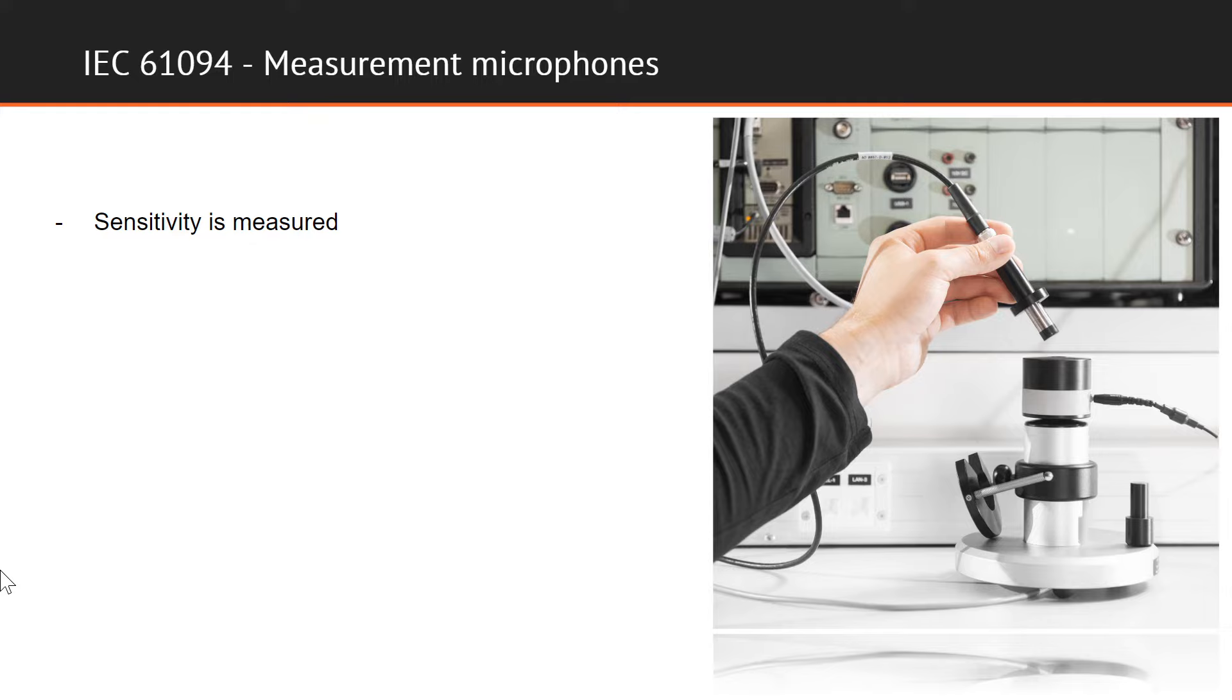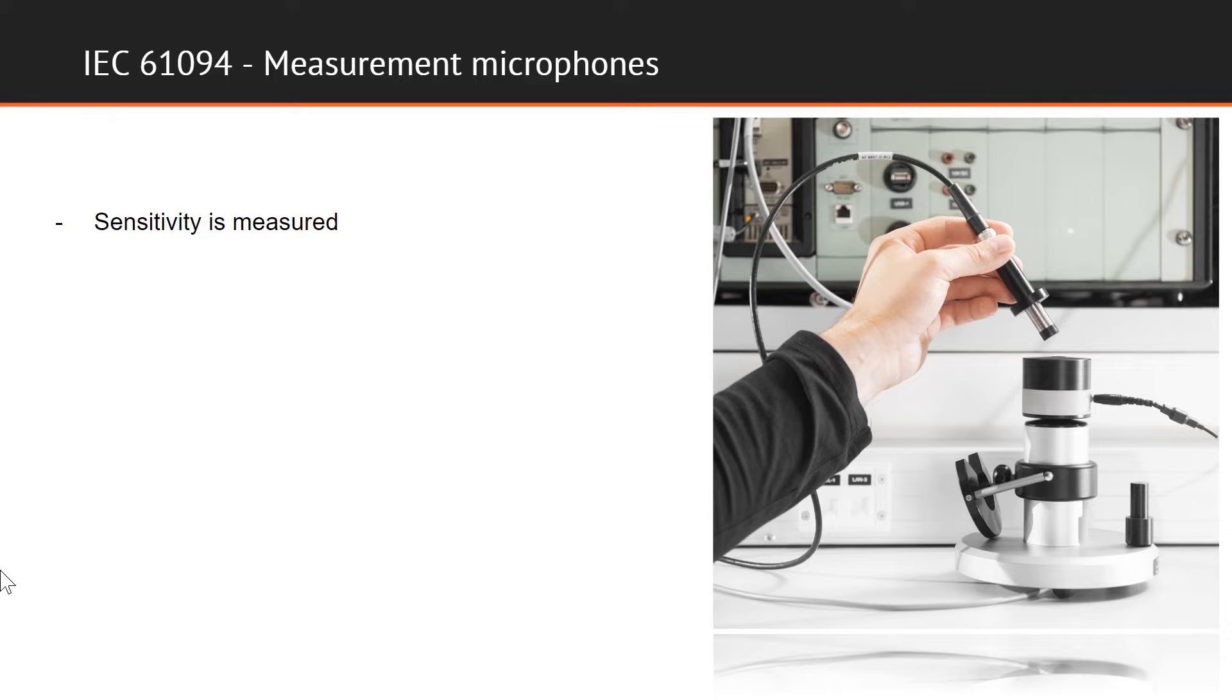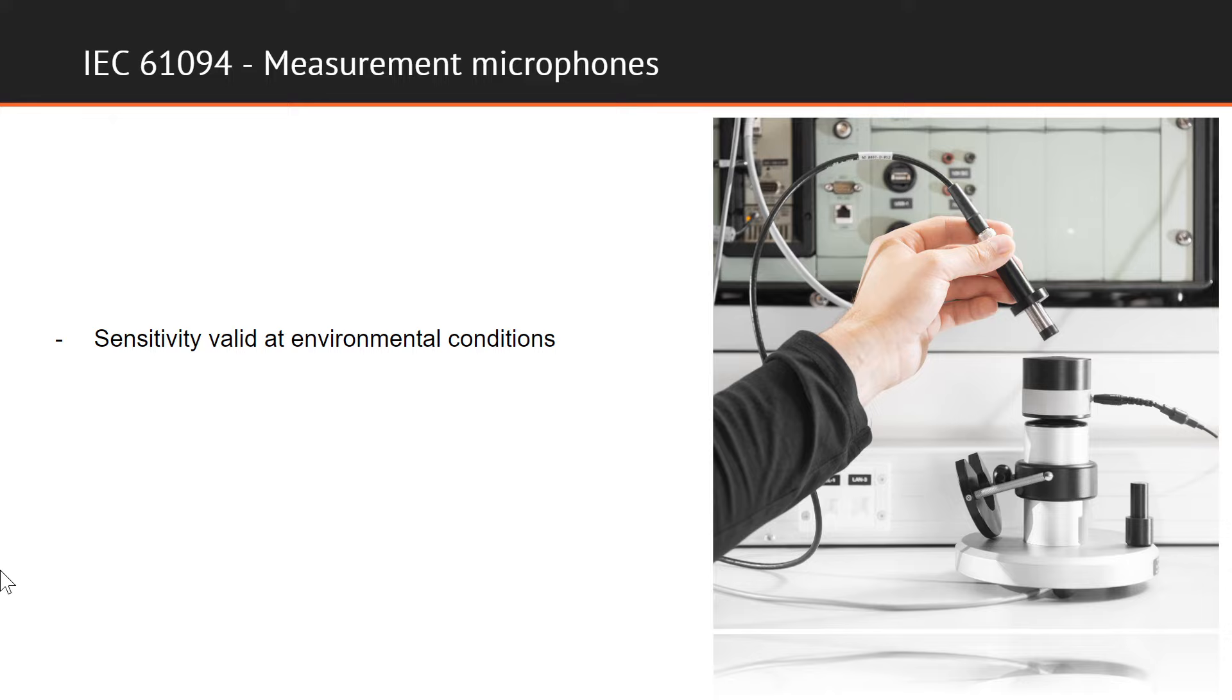The sensitivity of the microphone that is calibrated is measured by comparison with the reference microphone. The two microphones are exposed to the same sound pressure in an active comparison coupler, which contains a built-in sound source. The measurement frequency can be set to either 250 Hz or 1 kHz. The measured sensitivity is however valid at the environmental conditions during the measurement. Correction is made for the influence of environmental pressure, temperature, and humidity on the reference microphone.